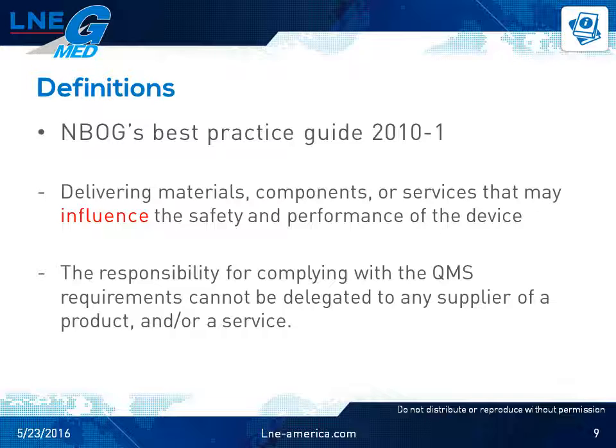This handbook guidance document for notified bodies focuses on auditing suppliers of medical device manufacturers. The document provides information on criteria, objectives, reporting, and examples of objective evidence notified bodies take into consideration when auditing critical suppliers as part of the legal manufacturer's certification process. Appendix 2 of this document provides insight on the supplier agreements and the provisions to be included. In any case, evidence of compliance of all certification scope activities remain the responsibility of the legal manufacturer and cannot be delegated to the supply chain.